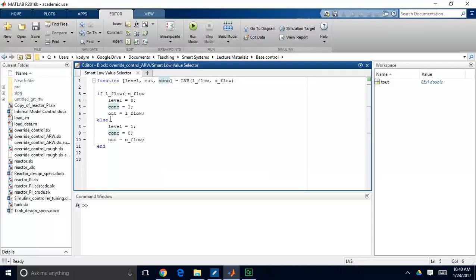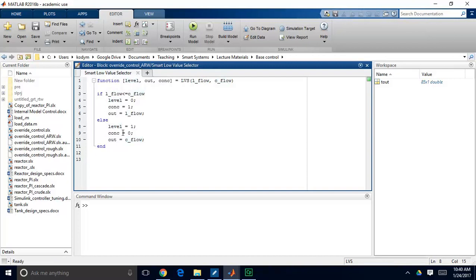So in the other circumstances, so when concentration flow is less than our level controller's flow, then we send a one to our level flow controller, and we send a zero to our concentration controller, and the low value that we pick is our flow signal from the concentration controller.